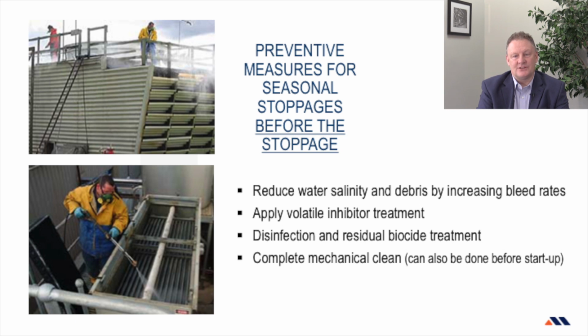This is also a perfect time for carrying out a complete mechanical clean of your cooling tower. If this is not done when the stoppage occurs, it must be completely done during startup, as it will eliminate any accumulated debris that needs to be removed from the water basin, the sprinklers, the fill, and the mist eliminator.